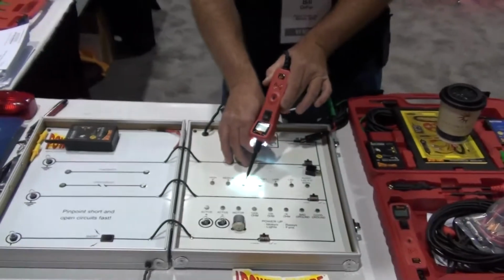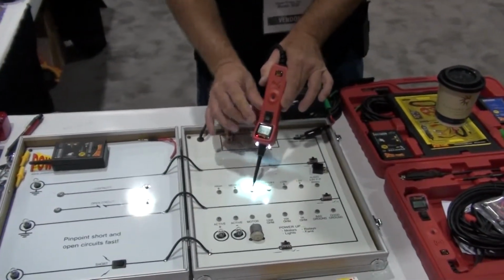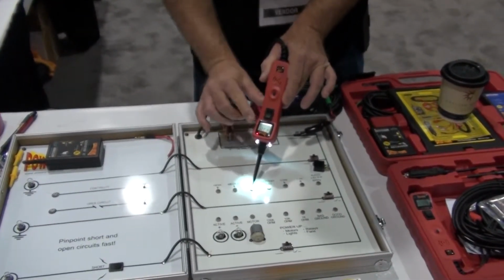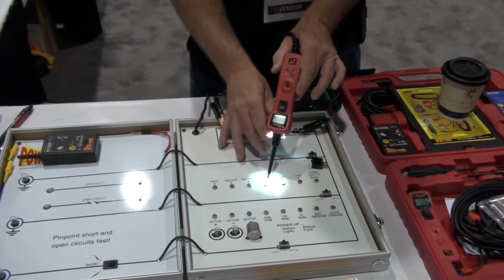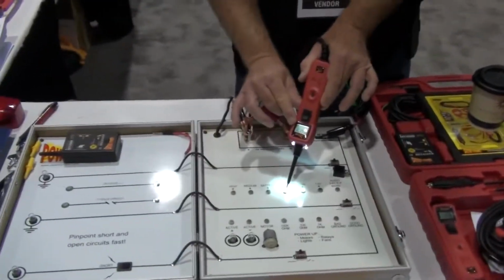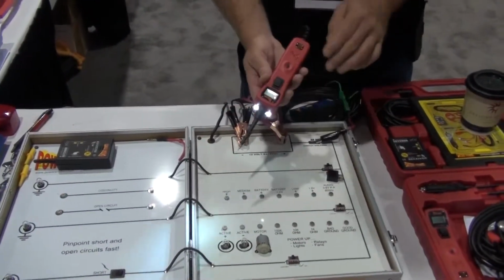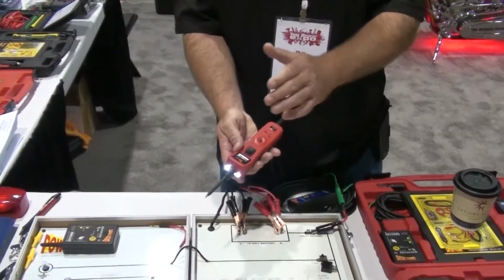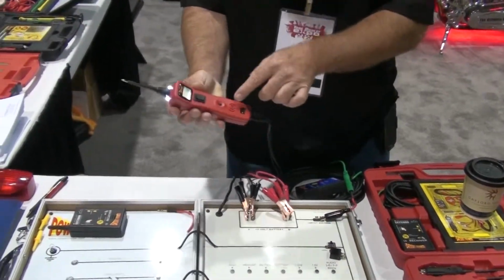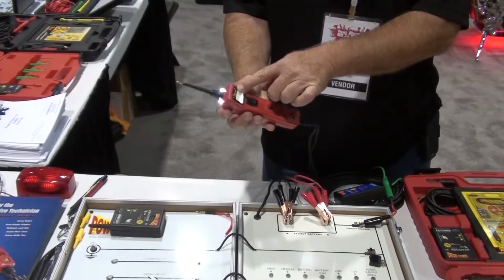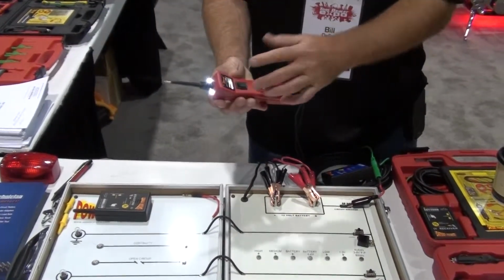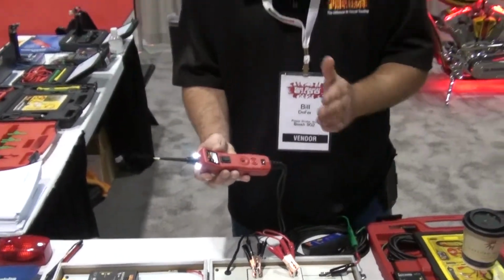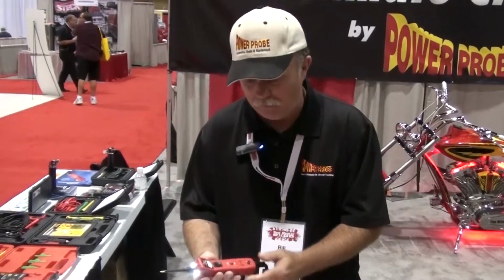Notice that when I probe into this, I'm getting a red light, I'm getting a tone, and I'm getting 11.8 volts. When I probe into this, I'm getting 10.5. If you're not within a half a volt of battery voltage, plus or minus a half a volt, you will get no tone, no LED, but you will see the readout. It tells you have a voltage drop in excess of a half a volt from battery voltage.